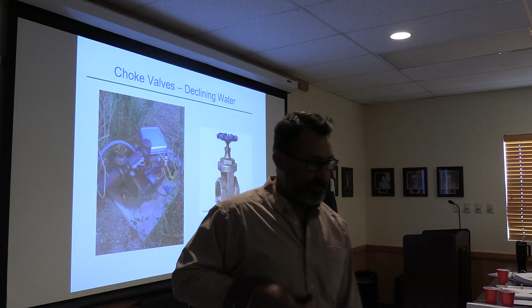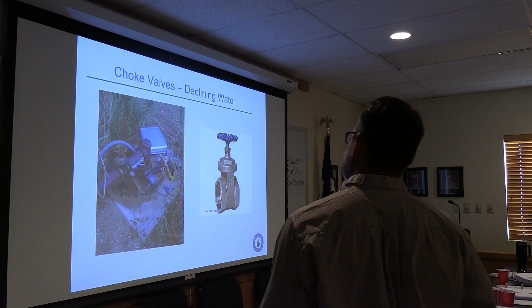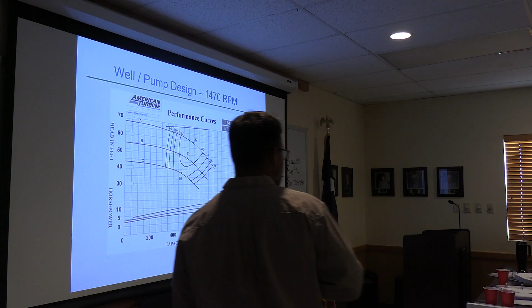It's a huge input on the pumping costs. It's a necessary evil, but I'd try to make it as less evil as possible if you can, by doing things like adding a drive to those in the cases where it fits. Other ones would be matching your pump curve to your available water, not in April, but in August.